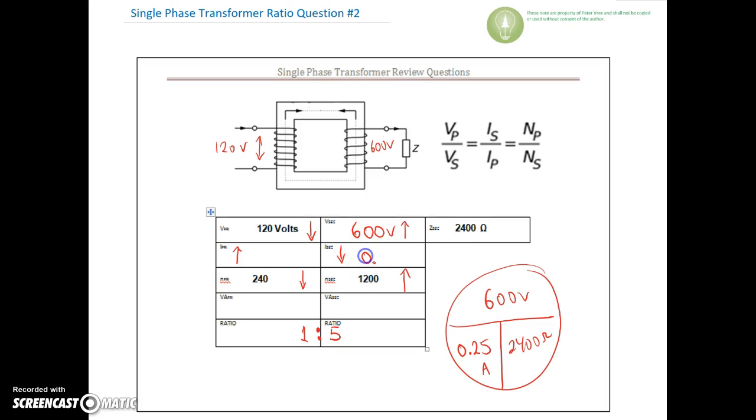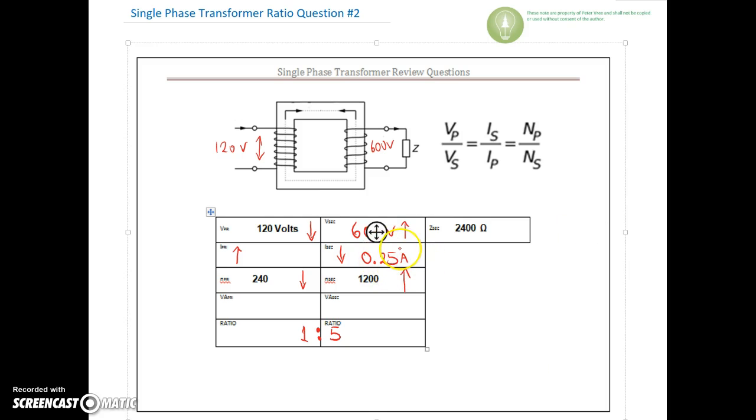Okay, so we've got 0.25 amps on the secondary, right? That's the lower current. Now we need to find out what our primary current is. So take a look, make sure everything's cool before we move on. Now if we look at the primary current, the primary current is going to be higher, and it's going to be higher by that same ratio. So it's going to be 5 times higher. So 5 times our secondary current of 0.25 gives us 1.25 amps on the primary.